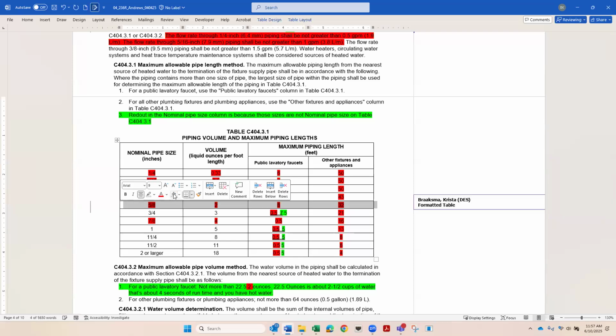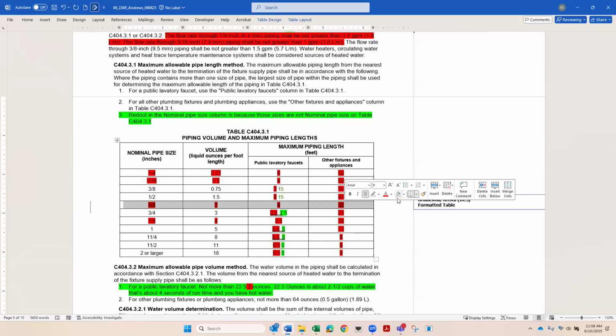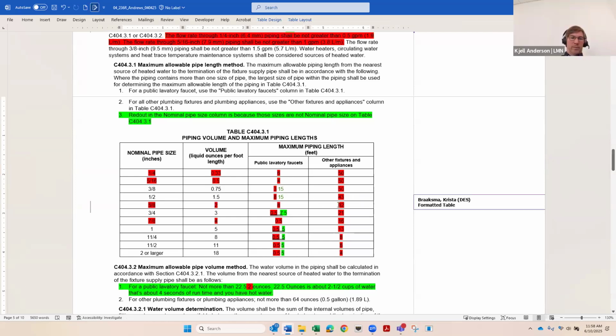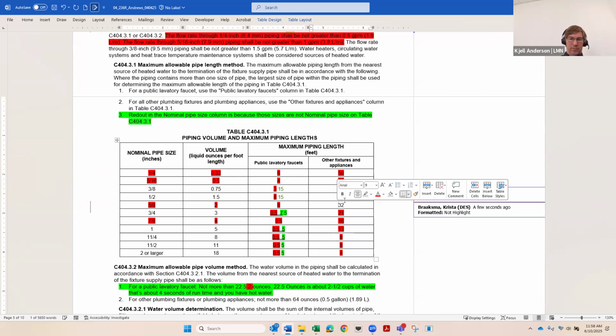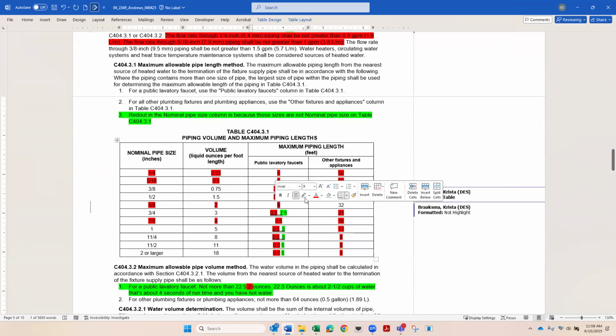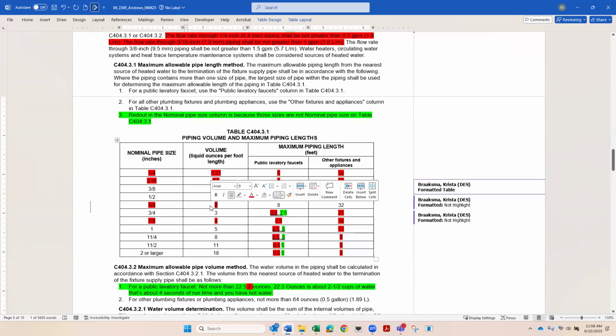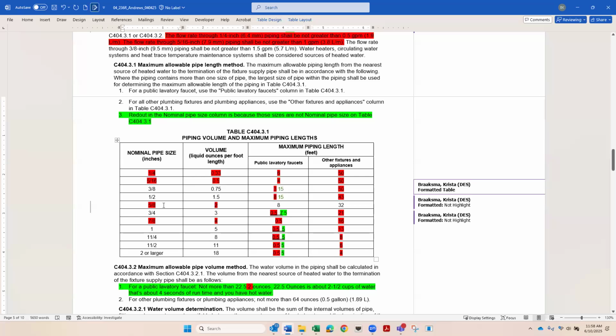Can I just say one thing? Yeah. On the plumbing side of things, this is what we're talking about - domestic hot water, domestic - it's not ever used. It's used in hydronic. The 5/8 was brought on for glycol systems and for loops, but it's not used in the plumbing, the potable water systems. We never use 5/8 out there, and it isn't even in the plumbing code. Okay, so that's why I eliminated it.